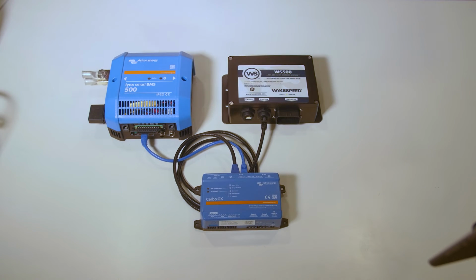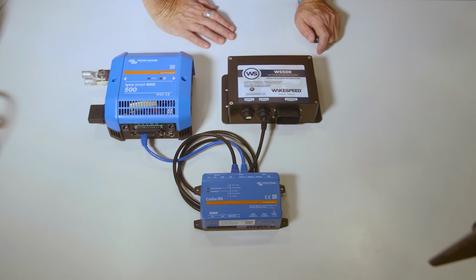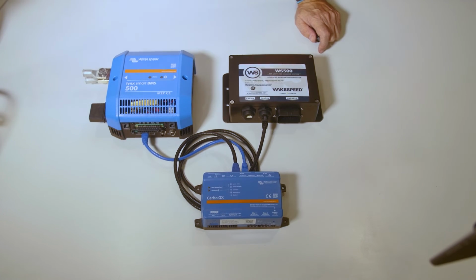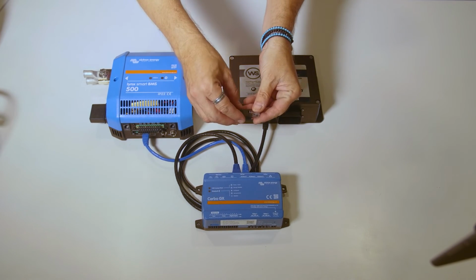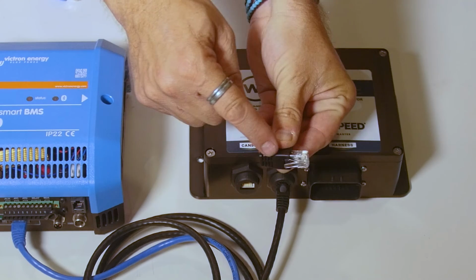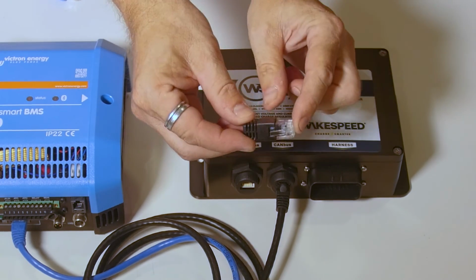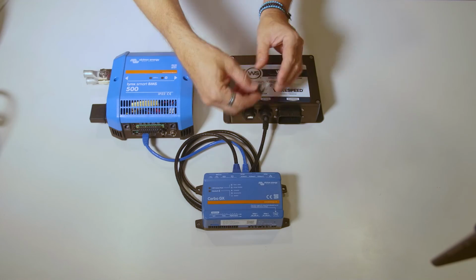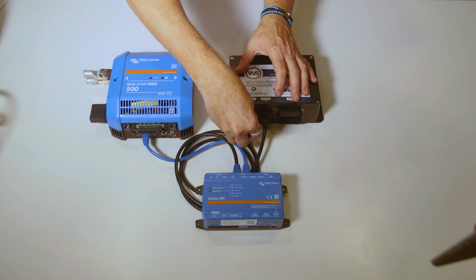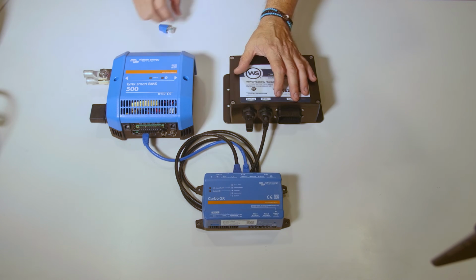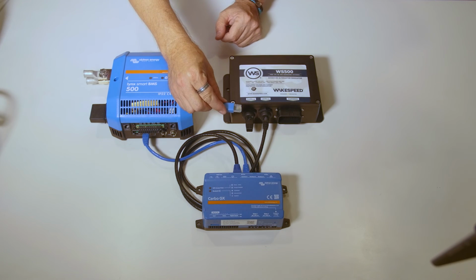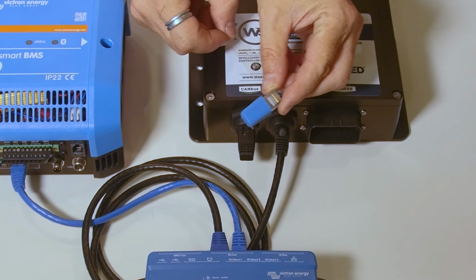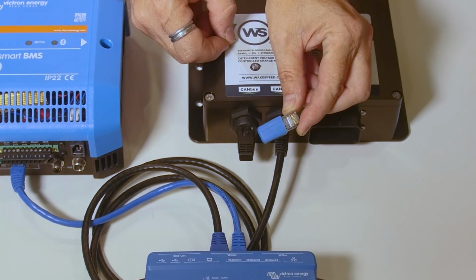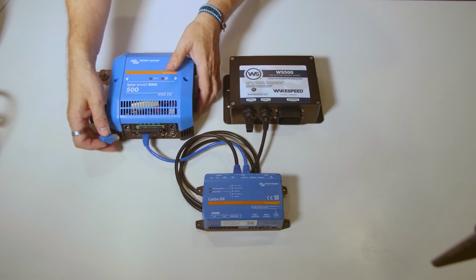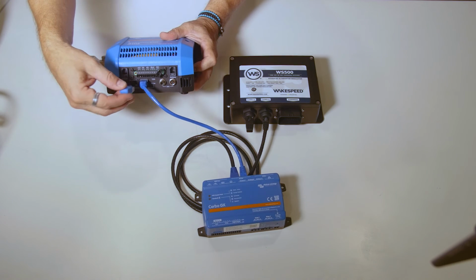Now, in CAN networks, you need to make sure that all unused ports are terminated. In your Wakespeed kit, you would have received a black data terminator - you're going to put that in the empty port of the Wakespeed. With your Cerbo GX, you would have received a number of these blue data terminators - you're going to put that in the one unused port in your Lynx BMS.